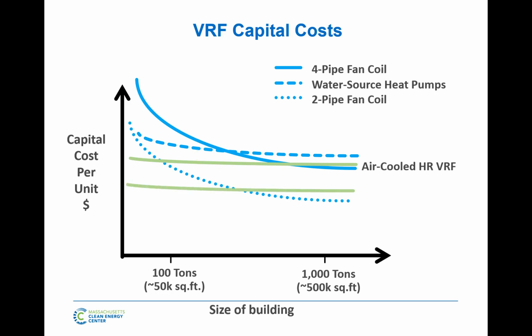Pull up the next one here, and it's a similar situation: a 4-pipe fan coil is equivalent to the air-cooled heat recovery, and a 2-pipe fan coil would be more equivalent to your air-cooled heat pump. So heat recovery is simultaneous heating and cooling. Heat pump is all heat, all cool. That's the most comparable system type to a 4-pipe, 2-pipe system. So when looking at first cost, there's always going to be that crossover point where, as a building gets to a certain size, a different technology might be more cost effective.